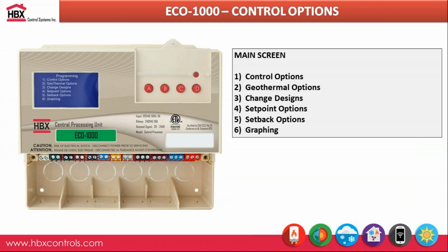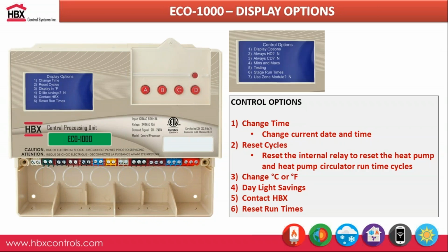So in terms of navigating through the controller, to get into your menu, you just want to press and hold down the C button, which gets you into your control options. So here you have 6 different options. You can see in graphing, you can access your setback and set point options. If you want to change your design temperatures in terms of your system, you can see that as well. And then we have your control and geothermal options.